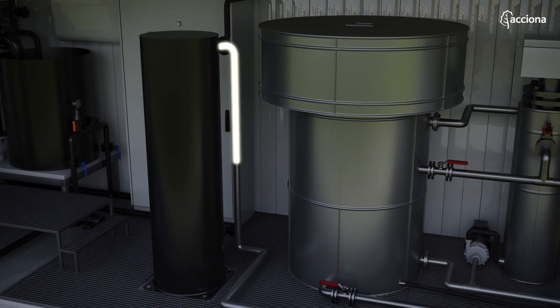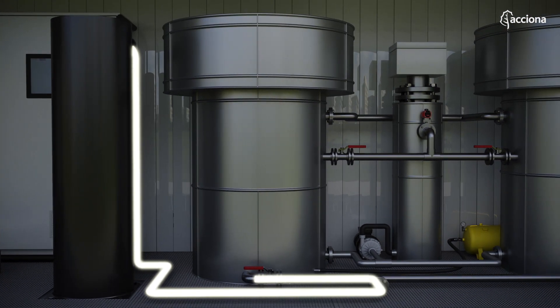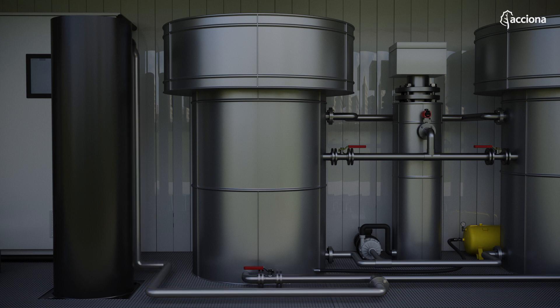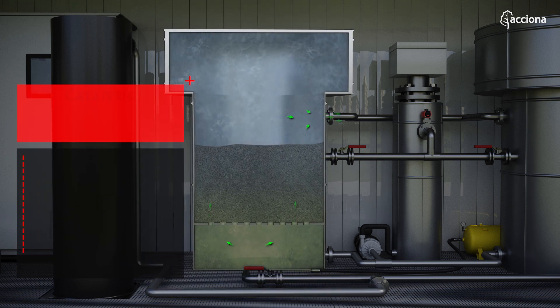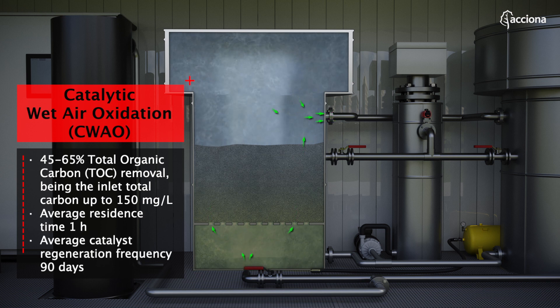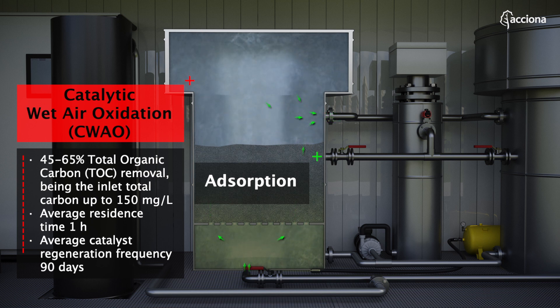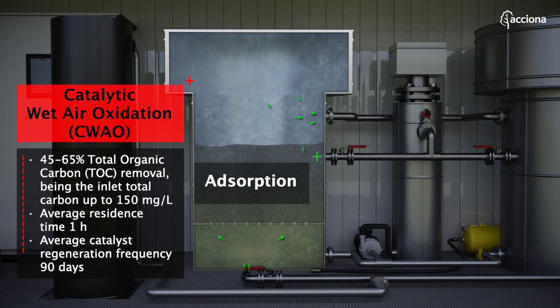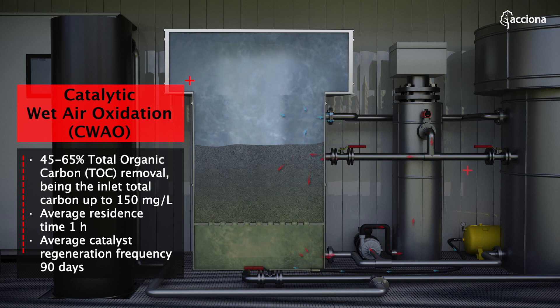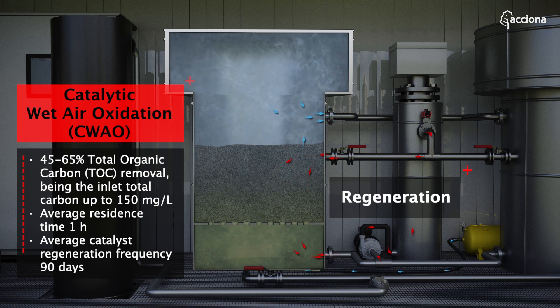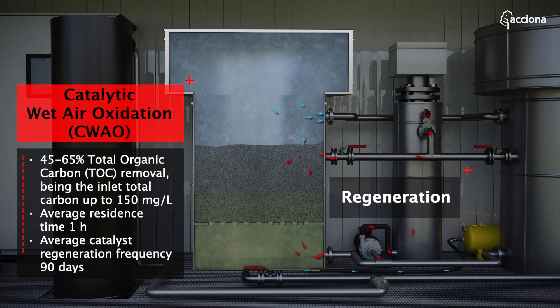Catalytic wet air oxidation is a continuous process that transforms the residual organic compounds into carbon dioxide and water without the generation of by-products. The water to be treated is introduced continuously into a reactor that contains a special adsorbent that also acts as a catalyst. Once the adsorbent is saturated, regeneration takes place where the adsorbed organic compounds are oxidized into carbon dioxide, avoiding the generation of by-products.